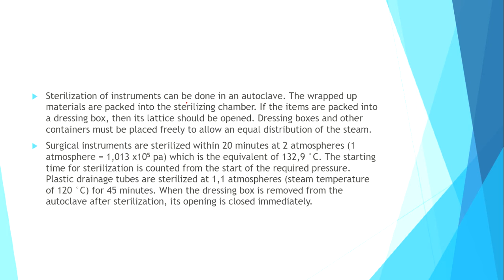1 atmosphere is 101.3 kilopascals, which is the equivalent of 132.9 degrees Celsius. The starting time for sterilization is counted from the start of the required pressure. Plastic drainage tubes are sterilized at 1.1 atmospheres, steam temperature of 120 degrees Celsius for 45 minutes. When the dressing box is removed from the autoclave after sterilization, its opening is closed immediately.